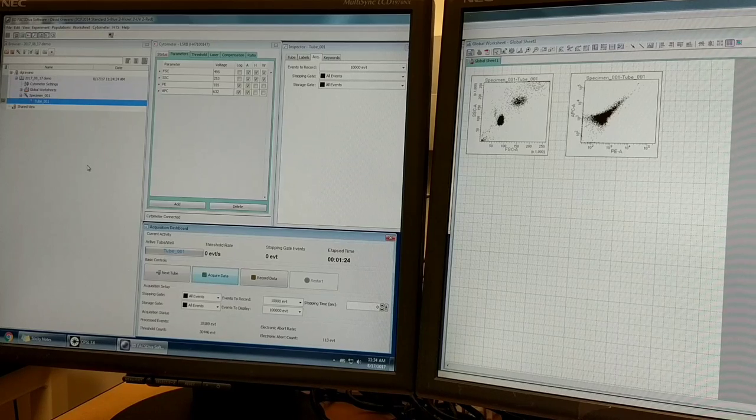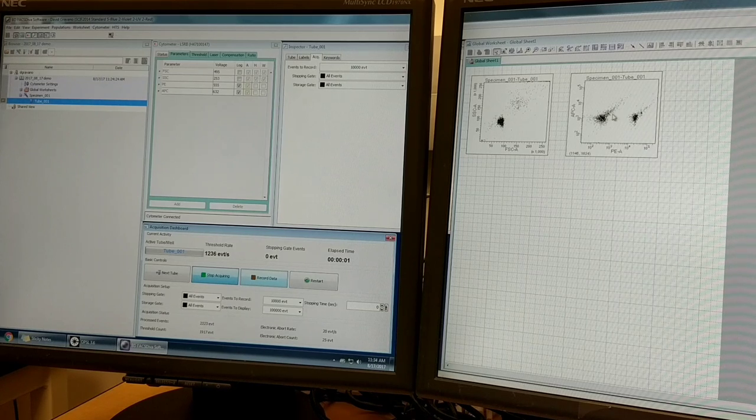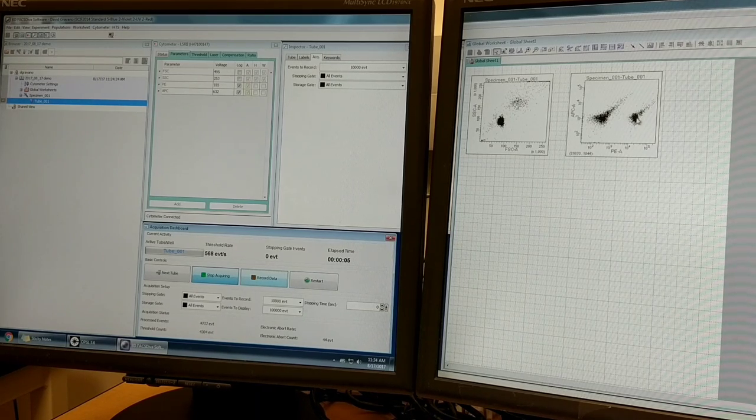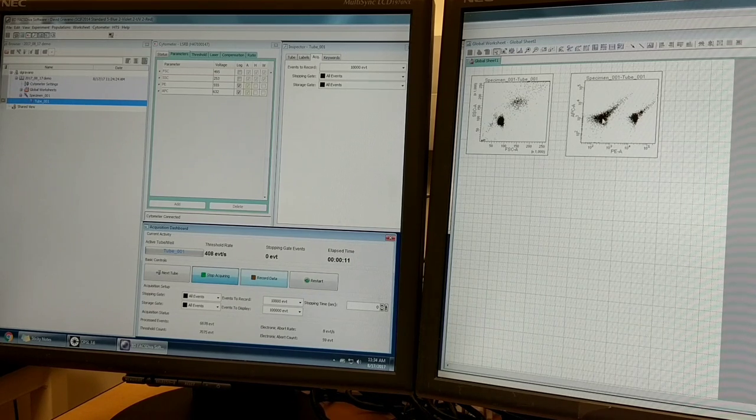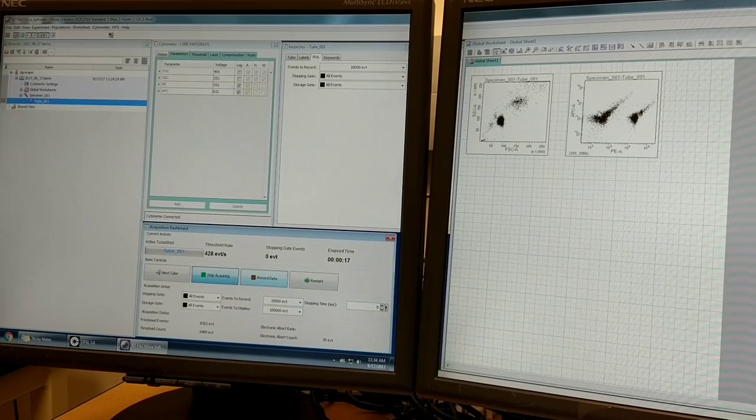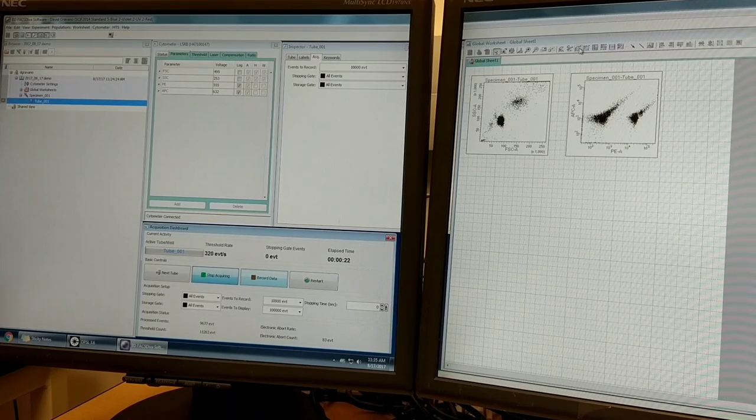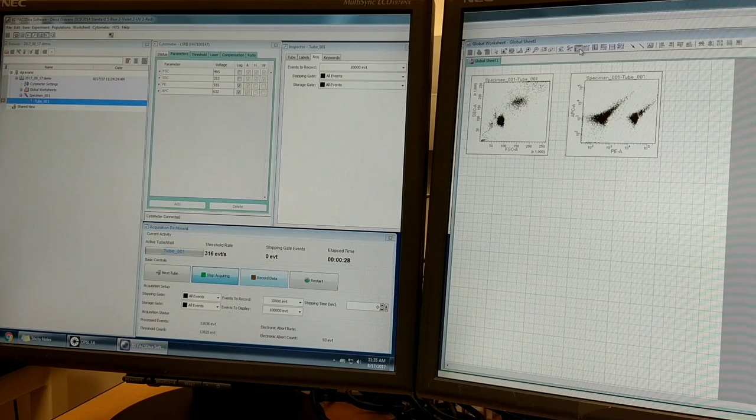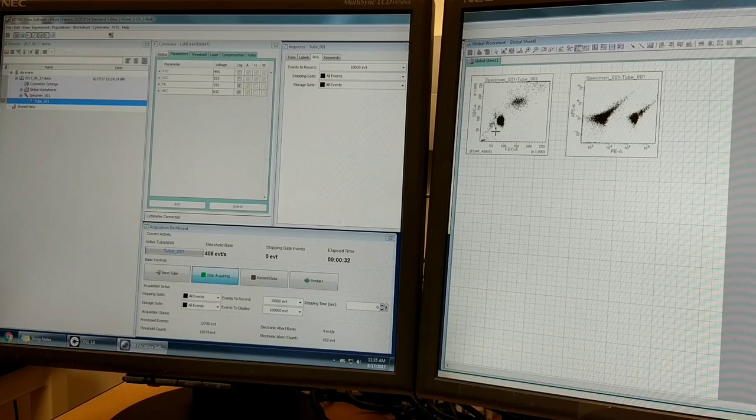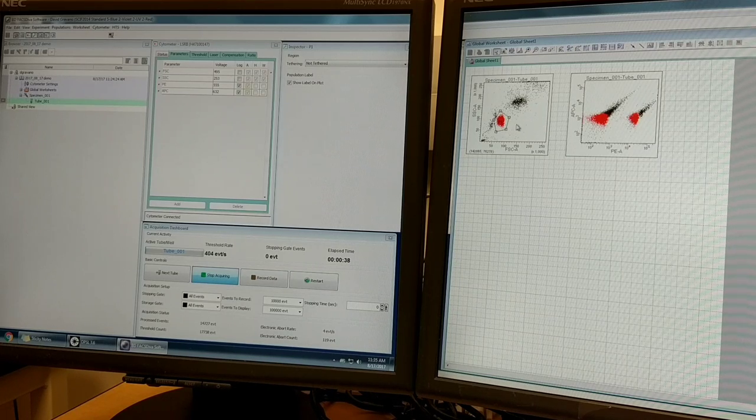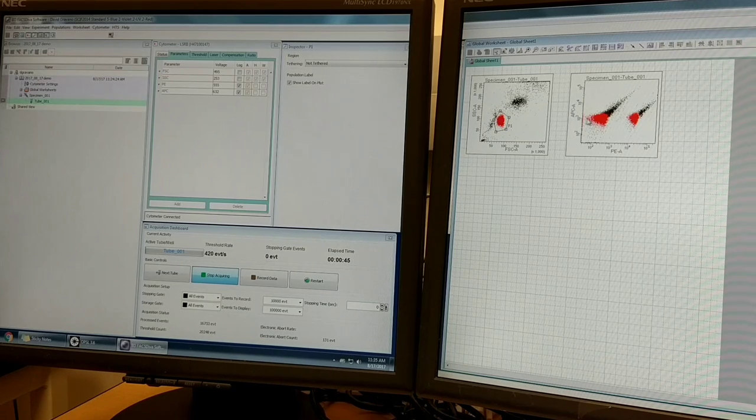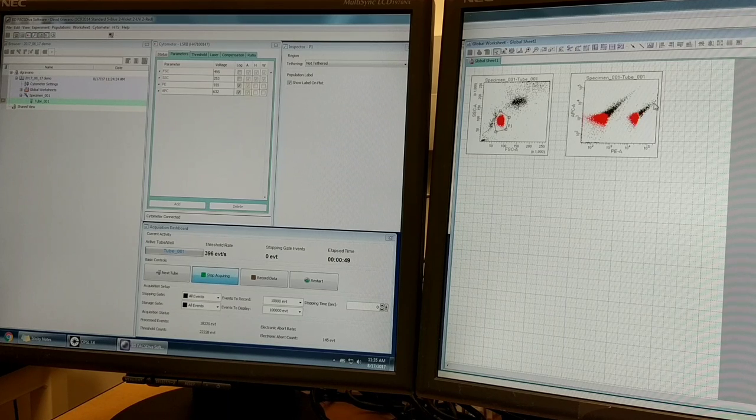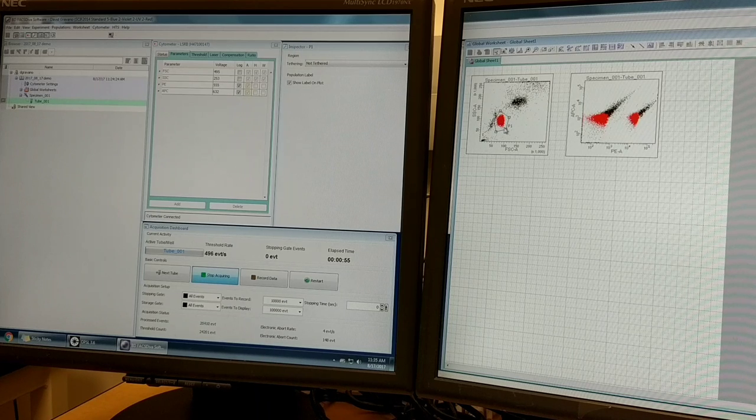I'm going to put the PE tube on and hit Acquire again. What I'm looking for is: is my PE signal bright enough while my background is low enough. You're really trying to maximize the distance between your positive population and your negative population. To help make this easier, I'm going to first draw a gate. The gating options are all up here. I'm going to draw a polygon gate around my population of beads that I really want. The rest is either doublet beads or degraded beads or other contaminants in the sample. So if I draw a box around this, which it calls P1, I can now see in red where those events fall.